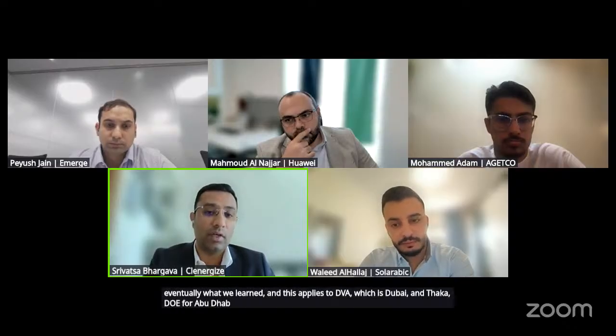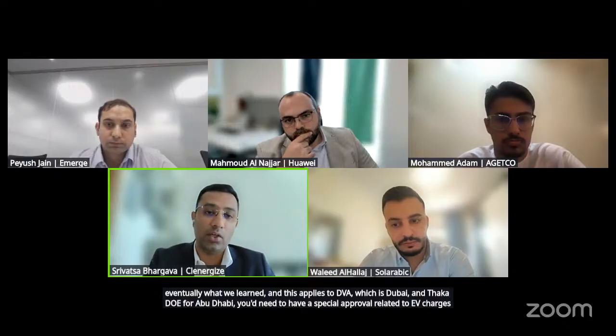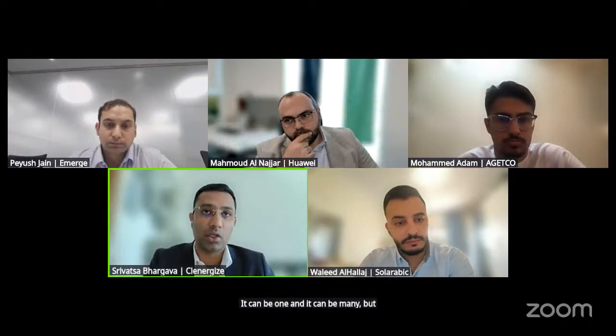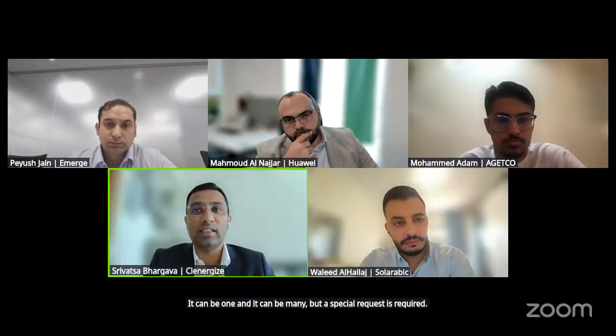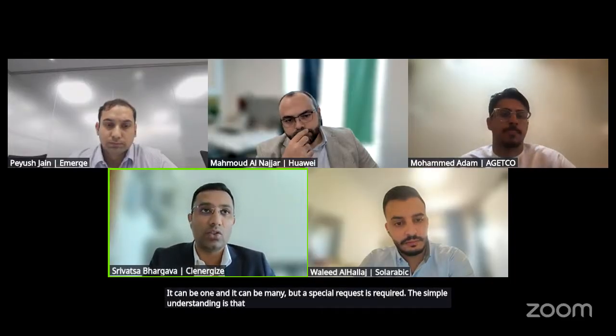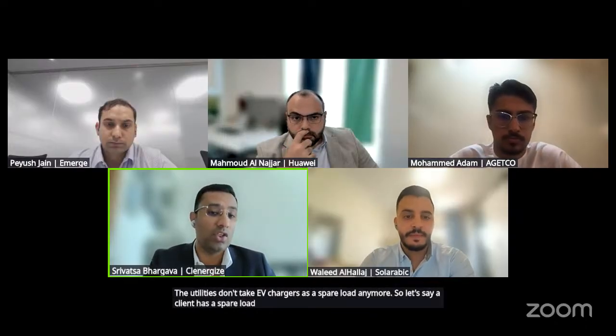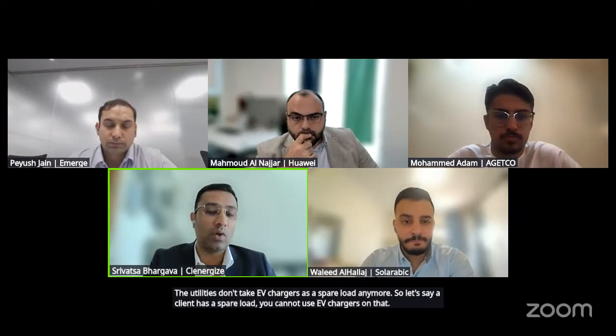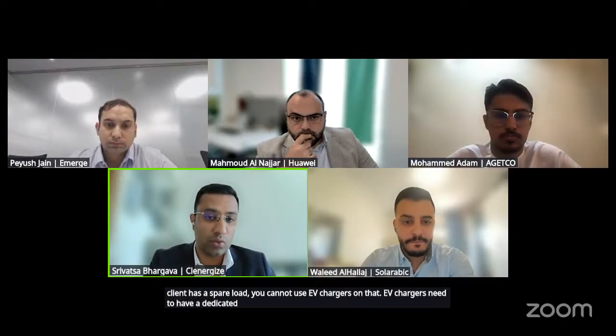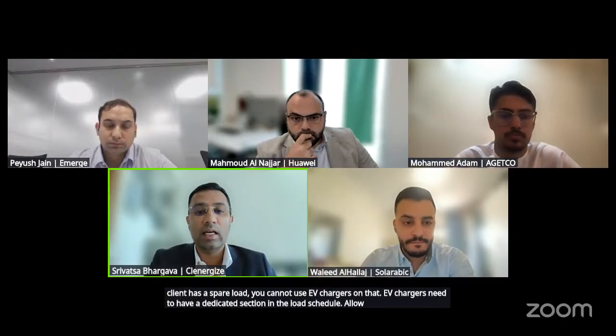you'd need to have a special approval related to EV chargers. It can be one and it can be many, but a special request is required. The simple understanding is that the utilities don't take EV chargers as a spare load anymore. So let's say a client has a spare load, you cannot use EV chargers on that. EV chargers need to have a dedicated section in the load schedule. Allow me to go a little technical on the load schedule to get the approval.